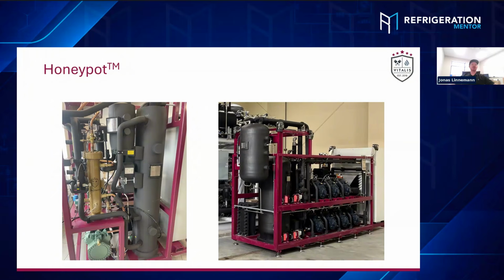Typically you want to start with a half-filled oil reservoir, either this style of oil reservoir or the normal style oil reservoir. You will have some sort of saturation of the entire field piping and evaporators with some oil, but the better the oil separation efficiency is, the less you need to refill. Once we implemented our optimized oil separator cartridges into the field, we heard a lot of feedback from installers that they had to remove oil which was already filled, and the system was running well. Once they got a higher efficiency oil separator, after a day they had to drain 1 or 2 gallons out of the system, because it all came back, never traveled into the system, and just accumulated in the reservoir. That's always a good sign when you can use less, because oil is super expensive.